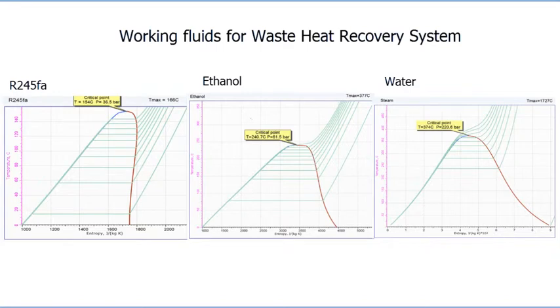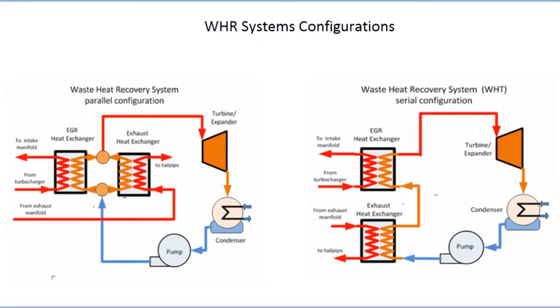The objective of the current study is to define a range of operating parameters — pressure and temperature — for each type of working fluid, and to compare a simple cycle with a more advanced cycle using recuperation. The following cases use an estimated heat rate specific to a combustion engine of 200 kilowatts of output power. The exhaust gas recirculation and exhaust heat sources are commonly used in waste heat recovery systems and may be connected in parallel or in series. The choice of particular configuration depends on engine design, and from the point of view of heat balance both configurations are very similar.